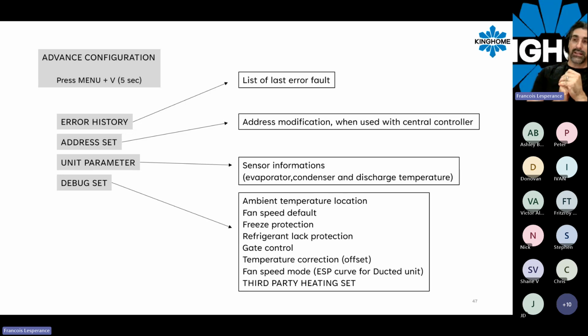In the unit parameter, this is where it's the good stuff, because on the search option, you just have access to the indoor room temperature and the outdoor temperature. But now with the sensor information, you also have access to the evaporator temperature, the condensing liquid line temperature, and the discharge temperature. So with all those 5 sensors, you are able to understand what's going on with the system. So why the system is operating like this, because this is what the sensors are reading right now. So that can greatly help when it's time to troubleshoot the unit, for example.